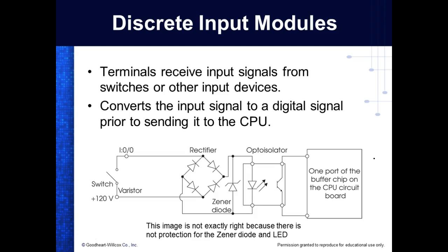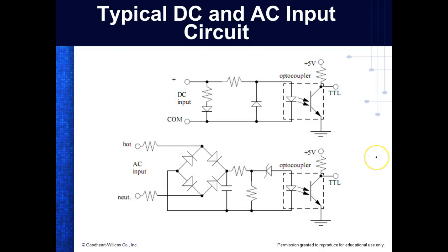So an actual true AC input port for a PLC actually looks like this. So what did we add to the middle? We added these things. Anybody know what these are? So now we've protected everything inside there. So this is the true AC input port. So the only thing your computer understands is DC. So if I'm going to have an AC input port, the first thing I've got to do is get it over to what? DC. This is called an optical isolator, optical coupler.